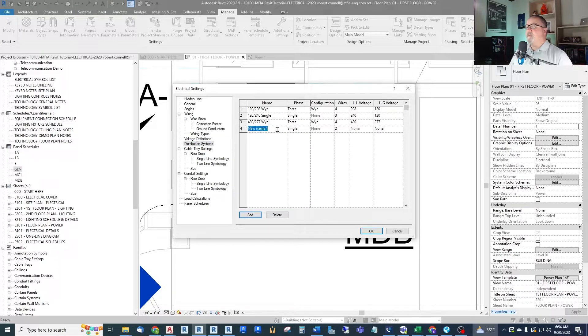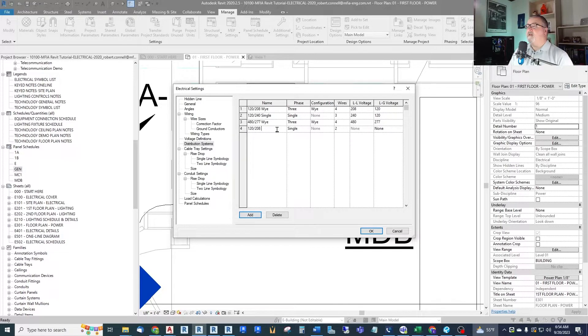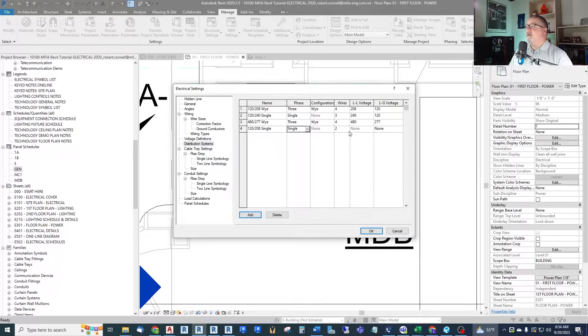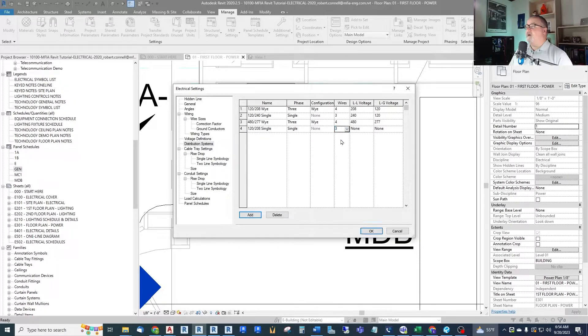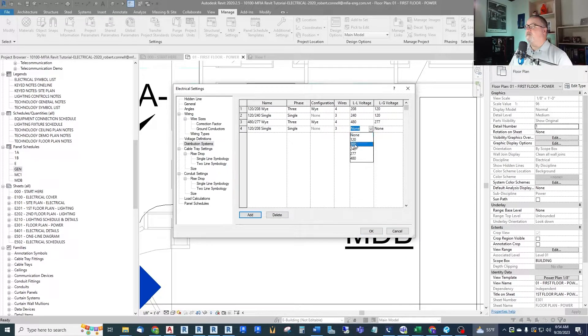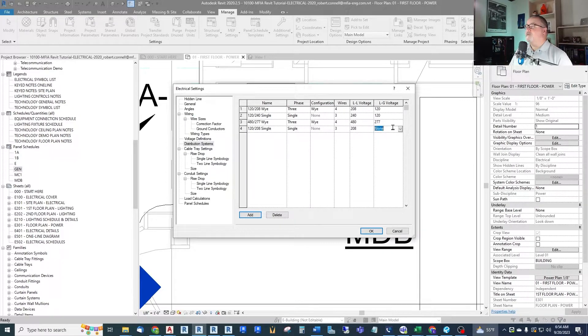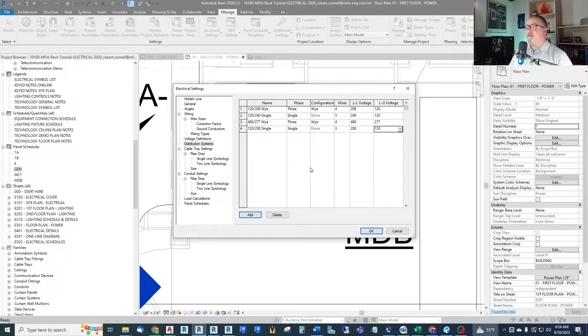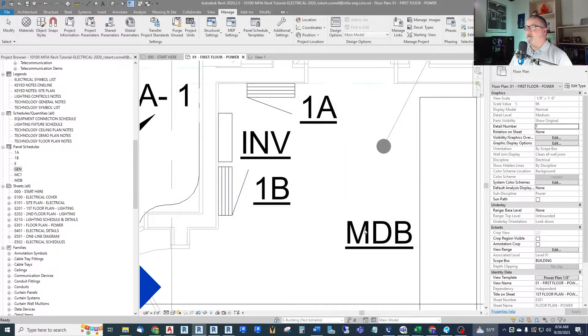And we will call it 120/208 single. It is single phase. We're going to make a three-wire system so we have two hots and a neutral. Line-to-line voltage will be the high voltage 208. Line-to-ground or line-to-neutral will be 120. So now we have defined another distribution system that our model can understand.